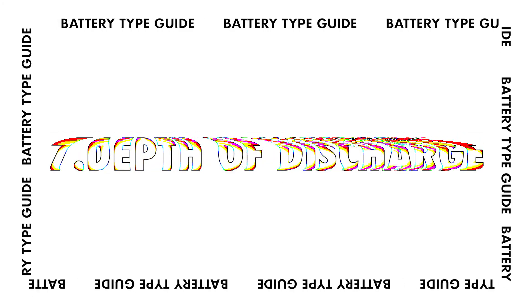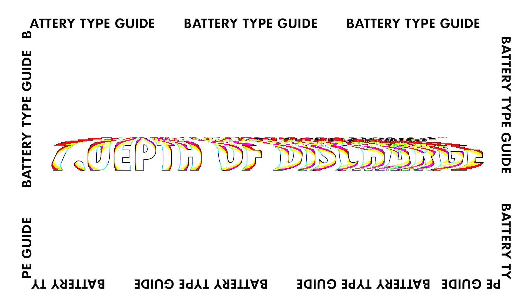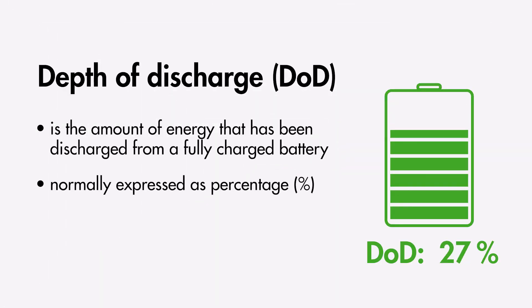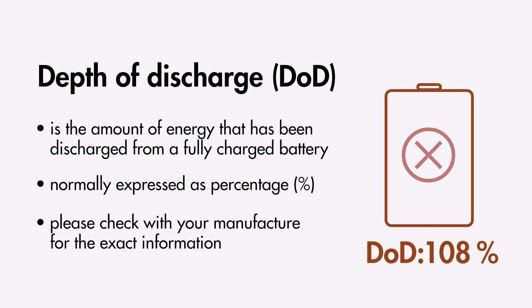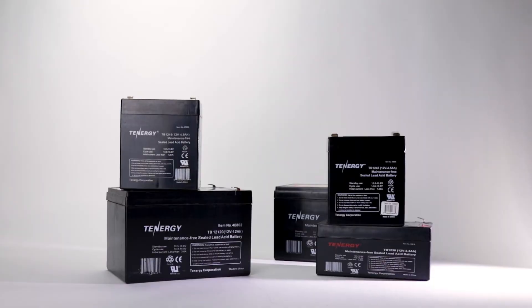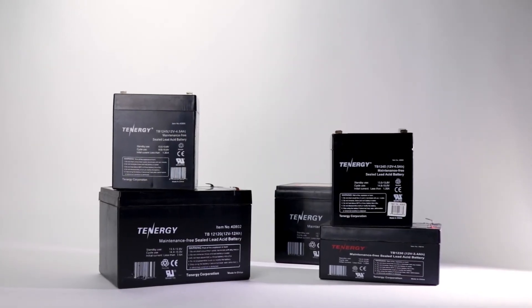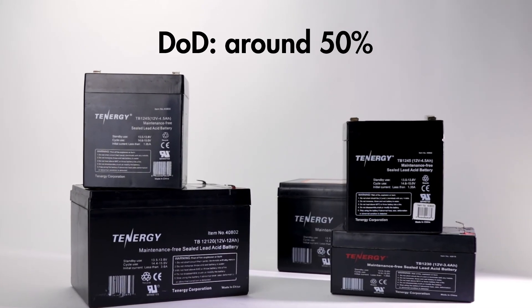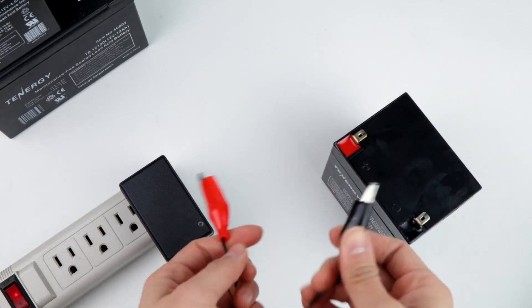Each battery type also has a different depth of discharge — the amount of energy that can be discharged from a fully charged battery, normally expressed as a percentage. A higher depth of discharge means more power can be drawn within a single cycle. If a battery is discharged beyond its maximum depth of discharge, it will affect performance and reduce lifespan. In particular, watch out for sealed lead acid batteries, since their depth of discharge is usually around 50%, meaning you should only use up to 50% of capacity before recharging to maximize performance.